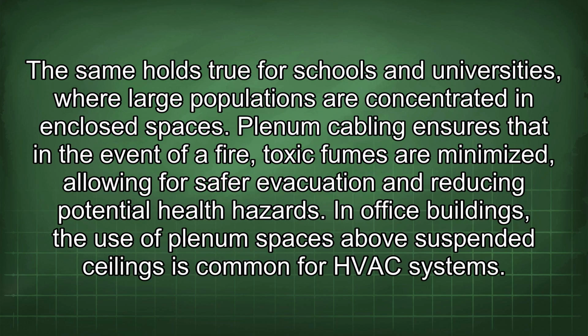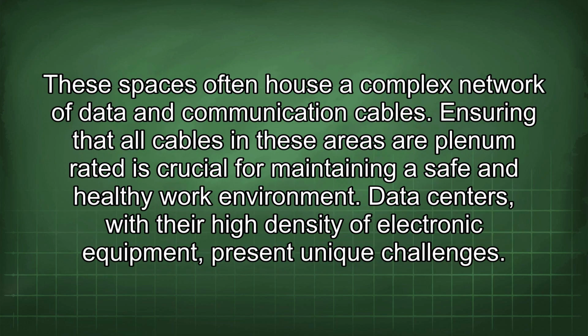The same holds true for schools and universities, where large populations are concentrated in enclosed spaces. Plenum cabling ensures that in the event of a fire, toxic fumes are minimized, allowing for safer evacuation and reducing potential health hazards. In office buildings, the use of plenum spaces above suspended ceilings is common for HVAC systems. These spaces often house a complex network of data and communication cables. Ensuring that all cables in these areas are plenum-rated is crucial for maintaining a safe and healthy work environment.